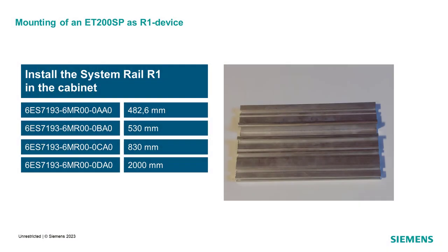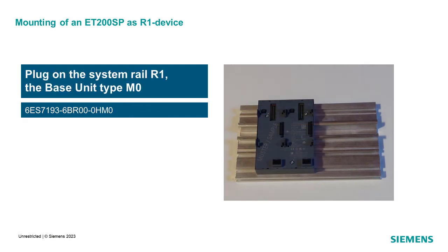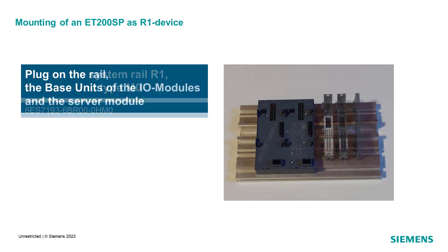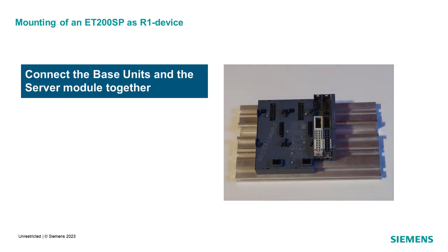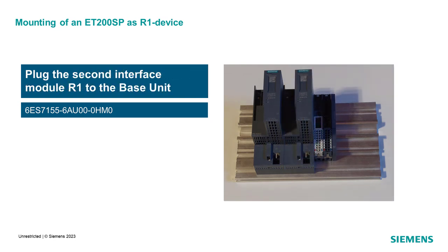First, install the system rail R1 in your cabinet. Different lengths are available. Plug on the rail the base unit type M0, dedicated for ET200SP R1 configuration. This one has two slots for the redundant interface module connection. Plug also on the rail all base units of the I/O module configuration, as well as the server module. At this step, every base unit required for the customer application is connected together.